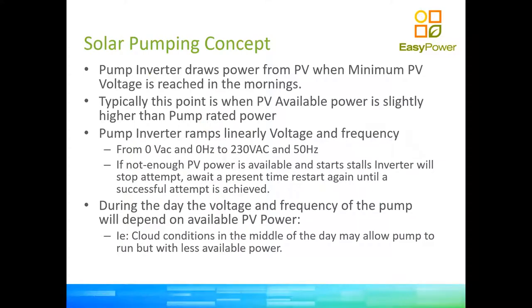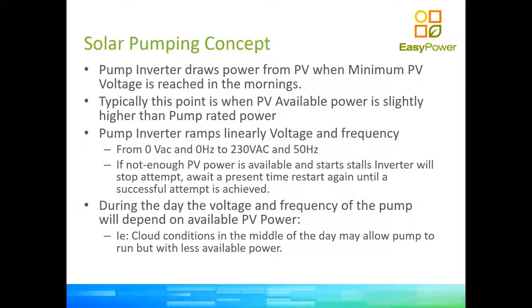Solar pumping takes DC power from solar panels and converts it to AC to run an AC pump. We can do AC pumps from 500 watts to 200 kilowatts. Typically a pump inverter changes the frequency of the pump — every motor or pump runs at about 50 hertz. The VSD starts at a low frequency of about 37 hertz, and as the day progresses and the voltage on the panels increases, it ramps up to 50 hertz at its peak. As the day winds down, it starts reducing frequency again.